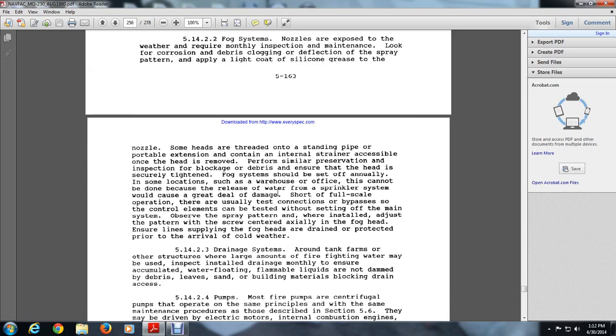514.23 Drainage system around tank farms and other structures. Larger amounts of firefighting water may be used. Inspect drainage monthly to ensure that accumulated water and floating flammable liquids are not dammed, and that debris and sand in buildings and materials do not cause blockage and restrict drainage access.